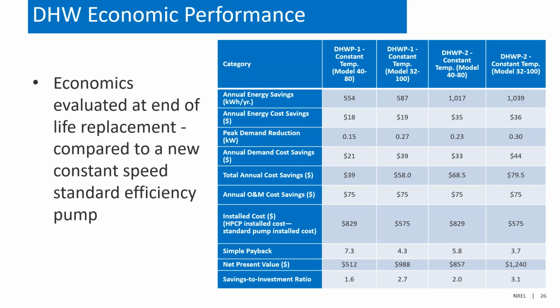So this just walks through the energy savings and economics here. The site did have a time of use rate structure, and so we have energy cost savings, demand reduction, and all of those things that are listed in here. The big driver for savings on this, though, was actually the O&M cost reduction. So you do not require greasing of bearings or have to replace pump seals on these. And so the on-site GSA staff estimated about $75 per year for O&M, and you can see it resulted in good economics across the board here.